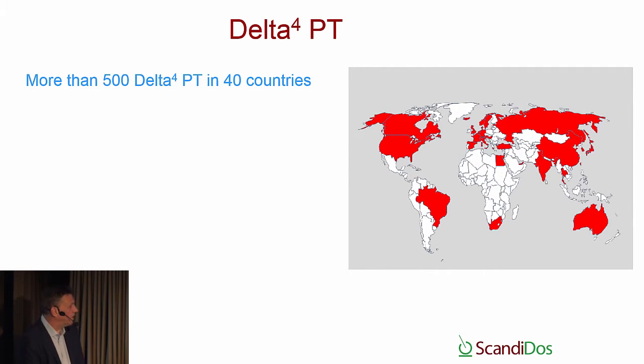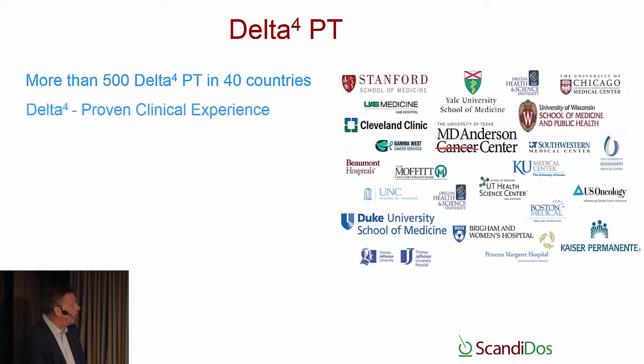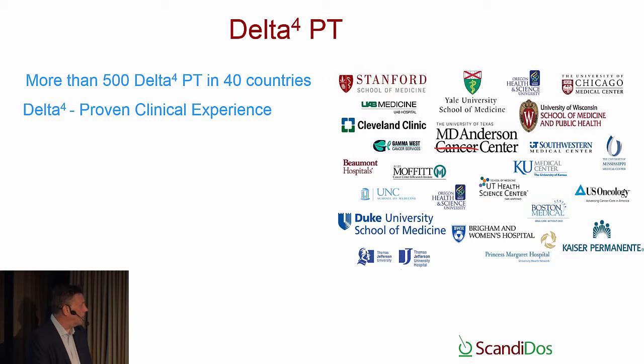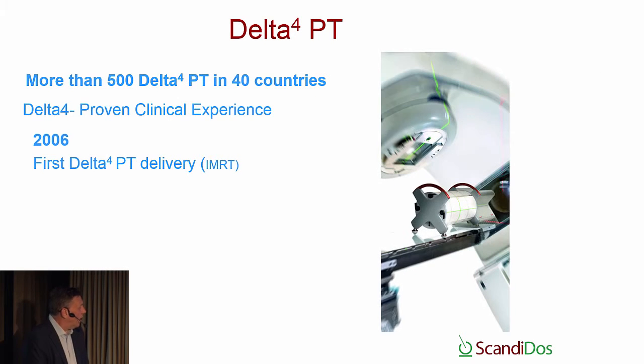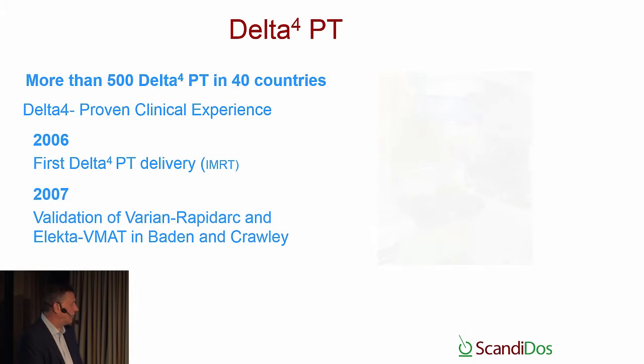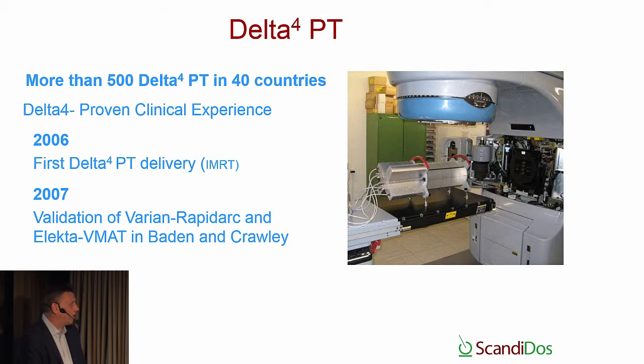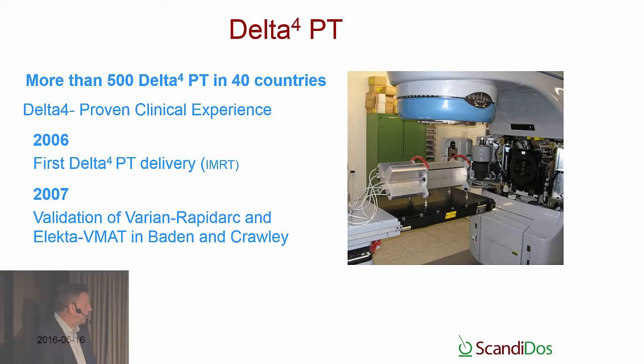Until last year, 2015, we had more than 500 Delta4 PT installed in more than 40 countries. In the US, we had a lot of proven clinical experience with partners that we've been working with. If we look backwards, already in 2006, we introduced the first Delta4 pre-treatment system, at that time for IMRT. Later on, we worked quite close with both Varian and Elekta on validating the VMAT and RapidArc technology. So we did factory testing together with them. And if you remember, they both released their products for VMAT and RapidArc in 2008.